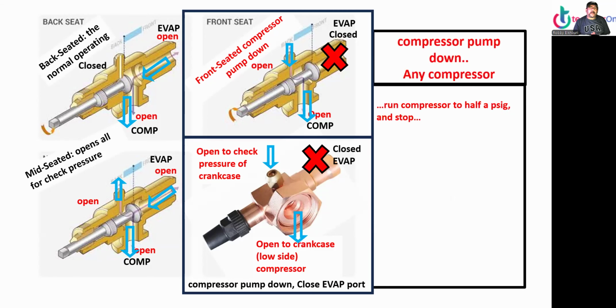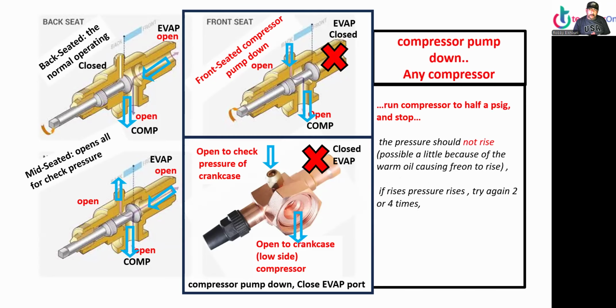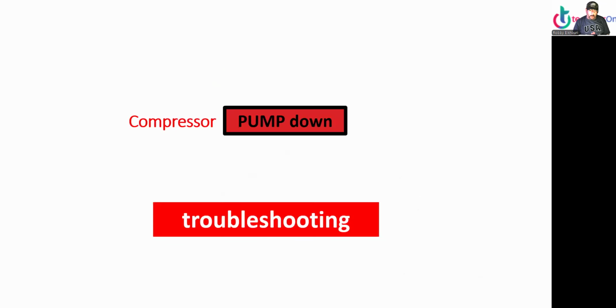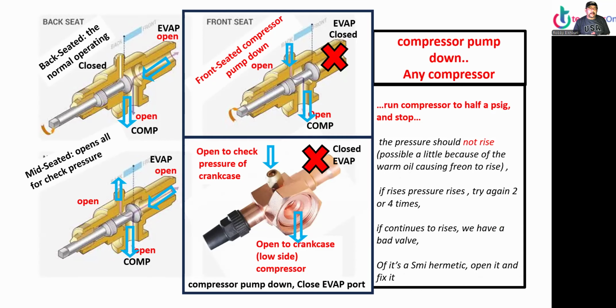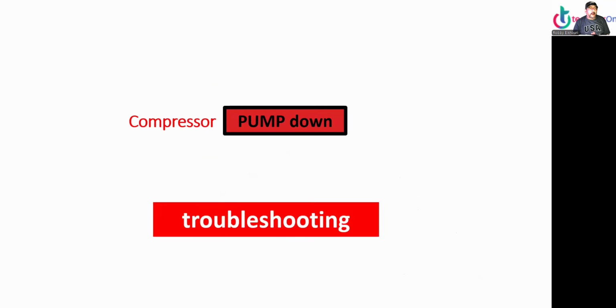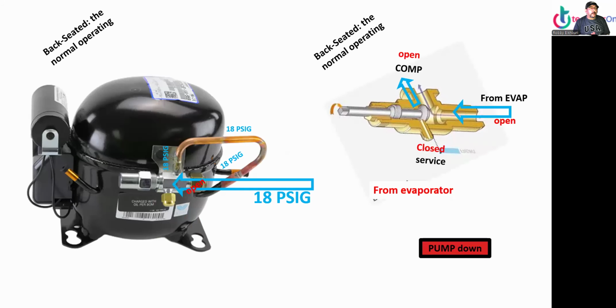Compressor pump down. Run the compressor to half a PSIG and stop. The pressure should not rise. Possibly a little bit because warm oil causes the Freon to rise. If the pressure rises, try again two or four times. If it continues to rise, we have a bad valve. If it's a semi-hermetic, open it and let's see, fix it. It could be just a broken valve. Could be something minor. All right, that's compressor pump down troubleshooting.